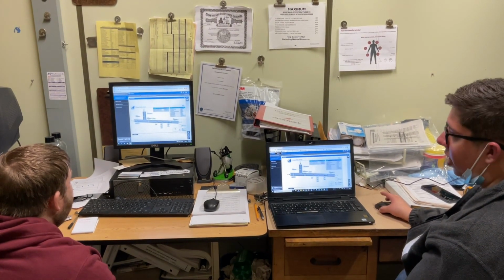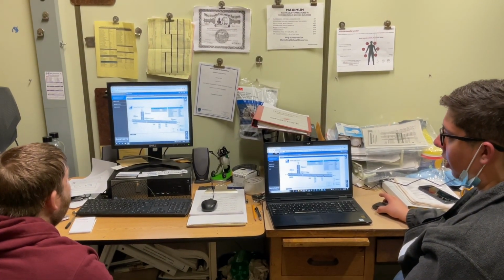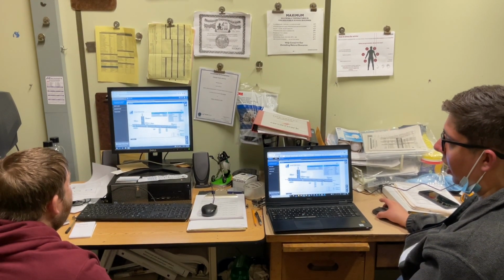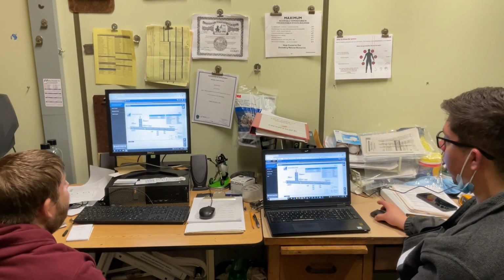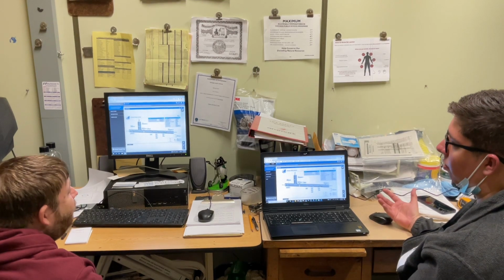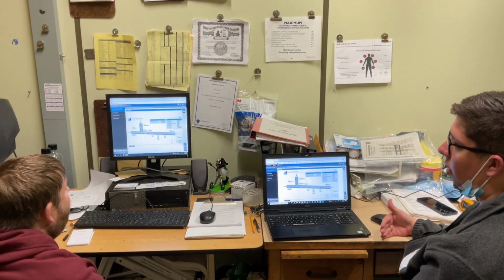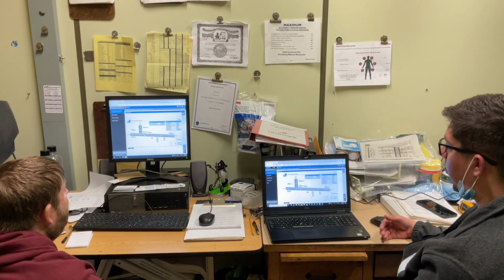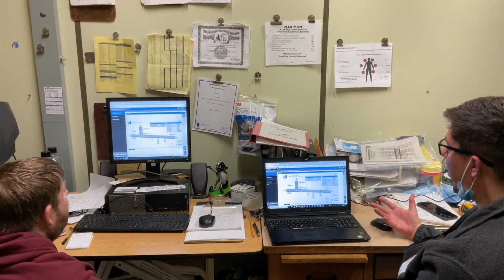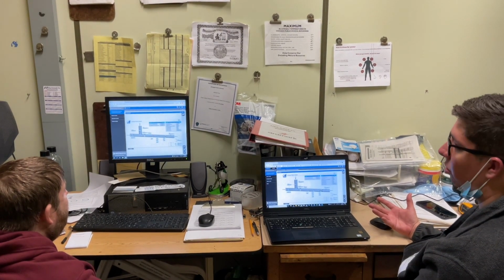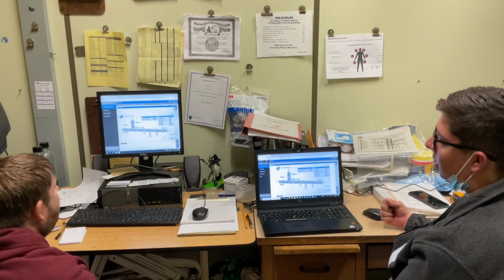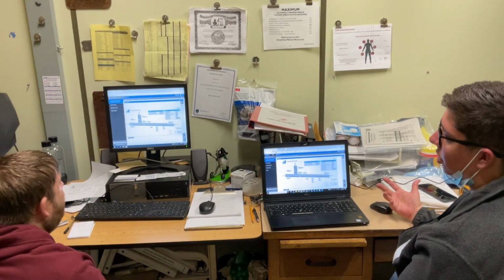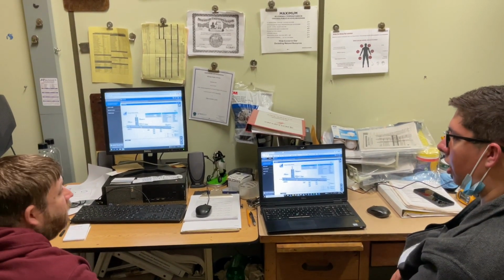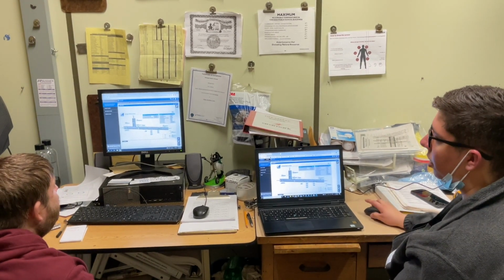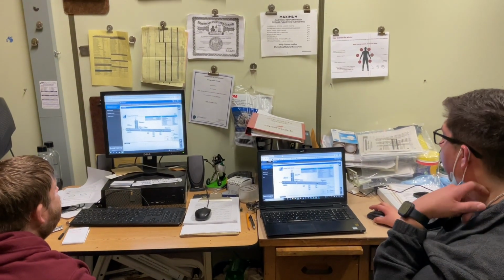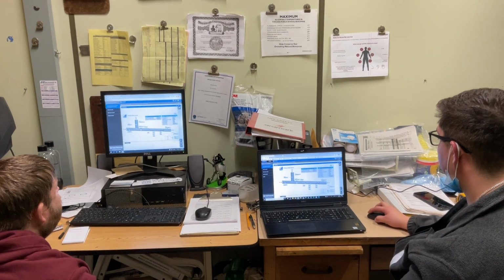Tuning reset, you should never really have to do anything with that, but just to note, if you were to do that tuning reset and turn it true, that basically just resets the logic on all the equipment. So really, the most you're going to be worrying about is heating and cooling stages. Say maybe the heating stages are taking way too long to stage up, you'd want to do a tuning reset. It just resets the timing that's inside the logic there.